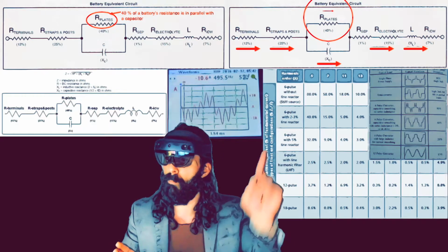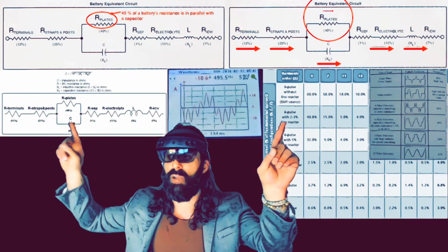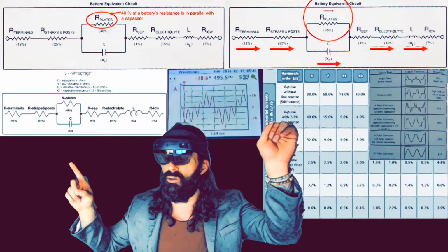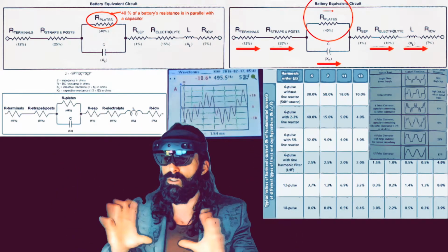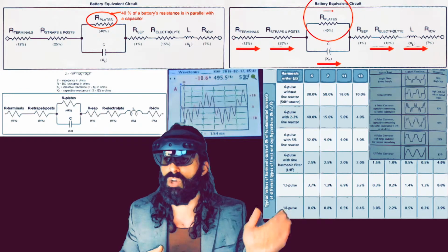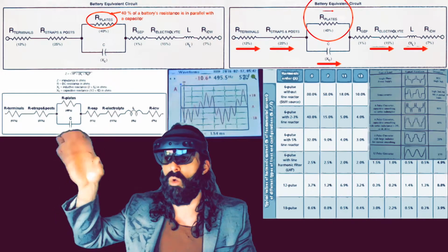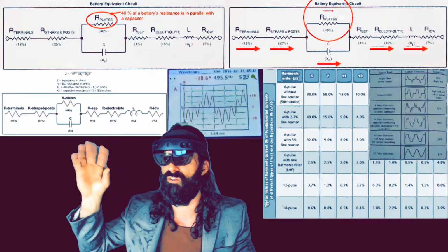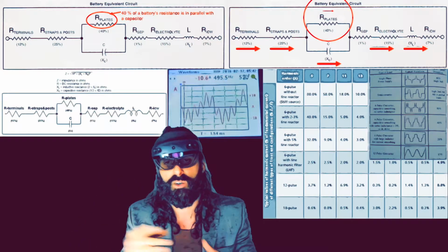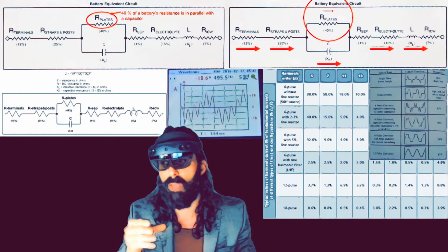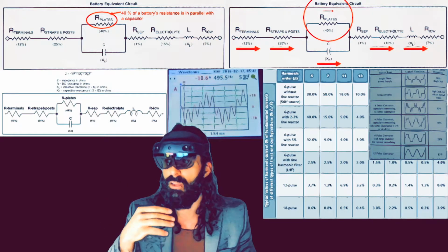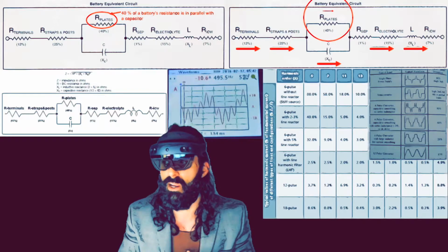So let's take a look at these two things above me at the top. You're going to see the battery equivalent circuit. On this side you'll see DC resistance, and on this side you'll see AC resistance. So what this is doing is breaking down the resistance within the battery material and internal components. You'll see terminal resistance, intercells at 12%, the straps and posts, intertiers at 25%, and then the plates of the battery internal, where you have 6 2-volt cells in a 12-volt monoblock. Those plates between the AGMs are 40% of the battery resistance in total. Then you have the separators, the electrolyte, the inductance, and again some intercell connections for the DC.